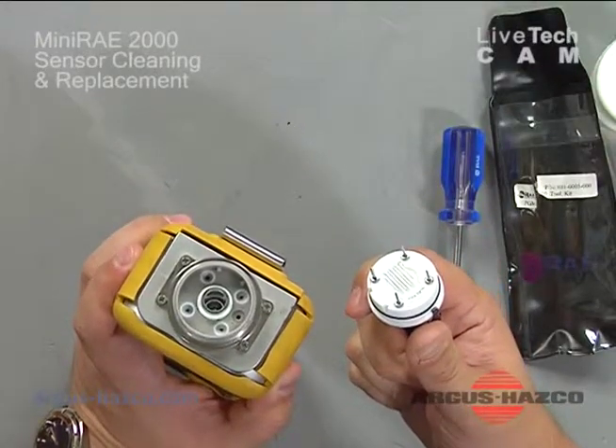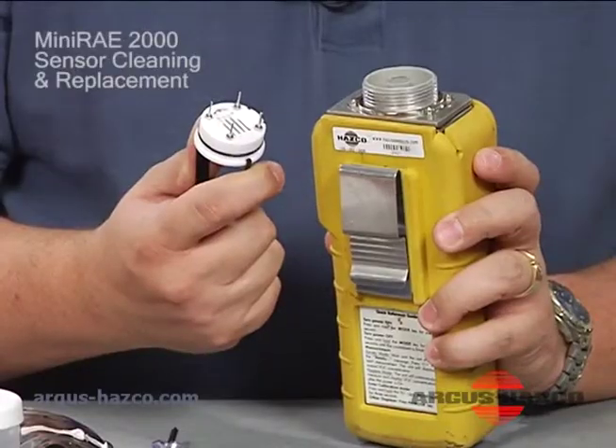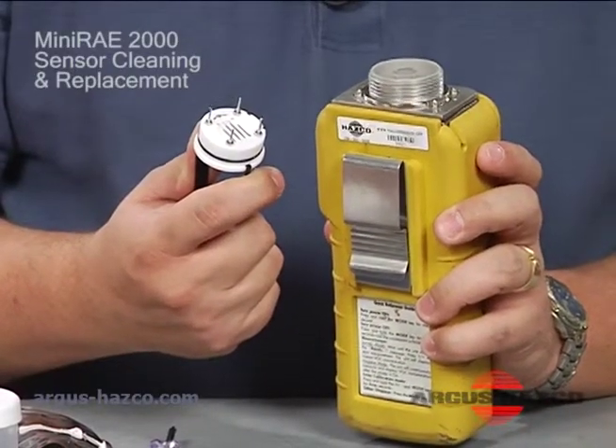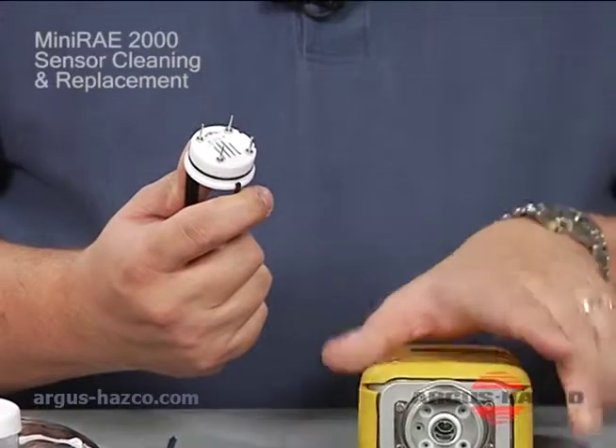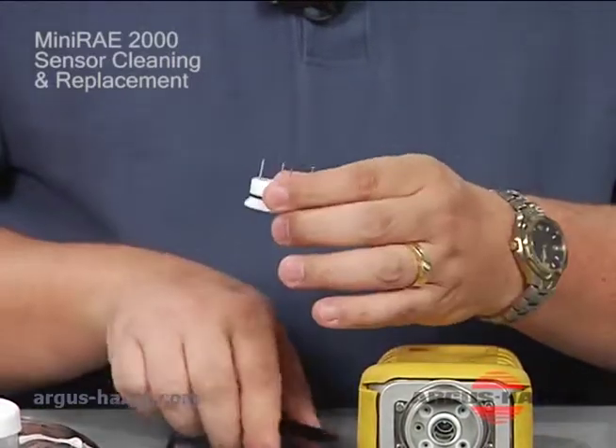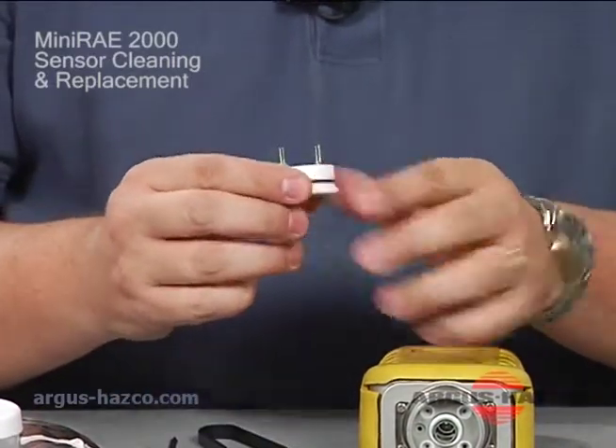You've exposed the lamp as well, so be very careful not to hit the top of that lamp or scratch it with anything. To clean the PID sensor, you can inspect it.